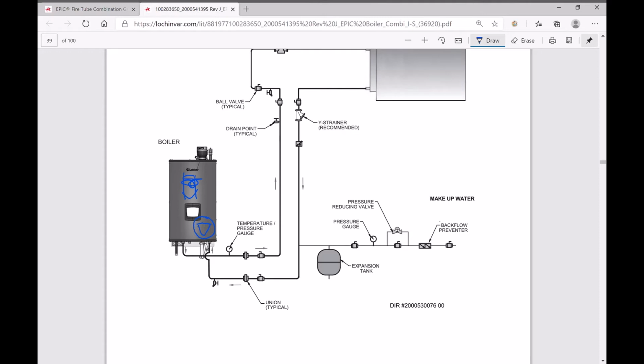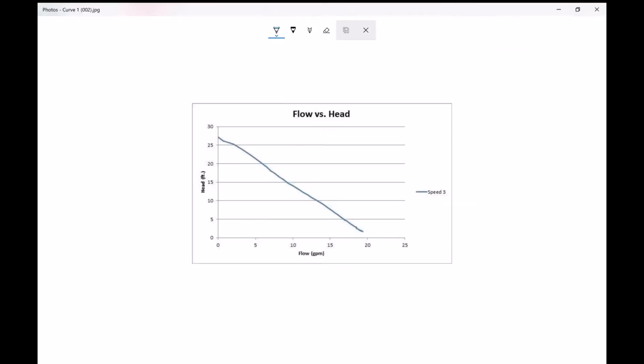But again, when we go back to the combi side, we can do this as well, and we'll look at the pump that comes with the combi boiler, and we can see that the maximum flow rate that we have on that pump is about 20 gallons per minute, and the maximum head we have is about, let's call it, 27 feet of head. This is a pretty large range for us to work with.